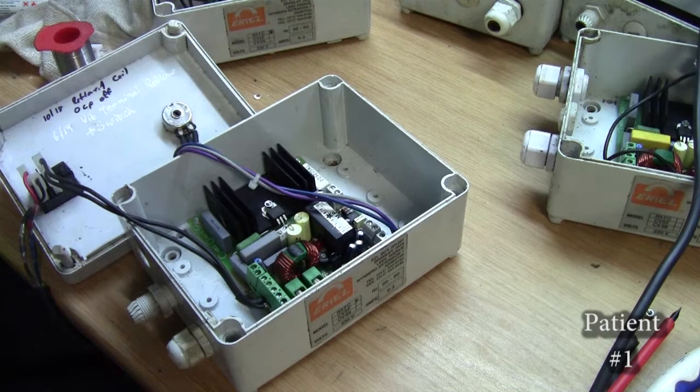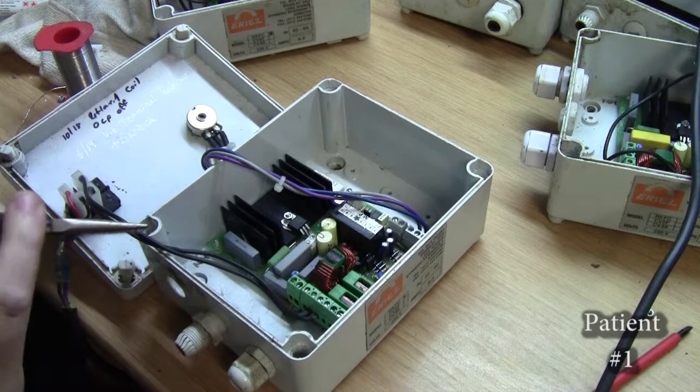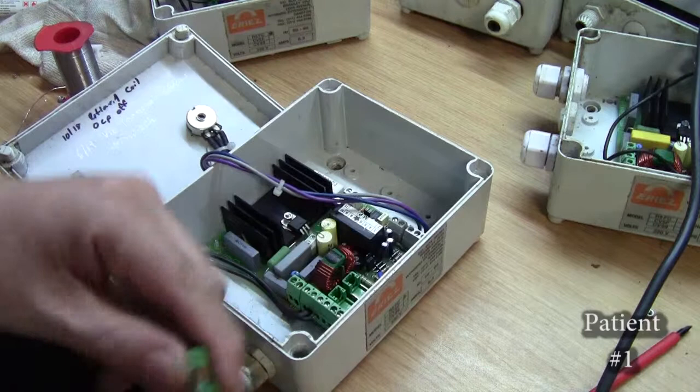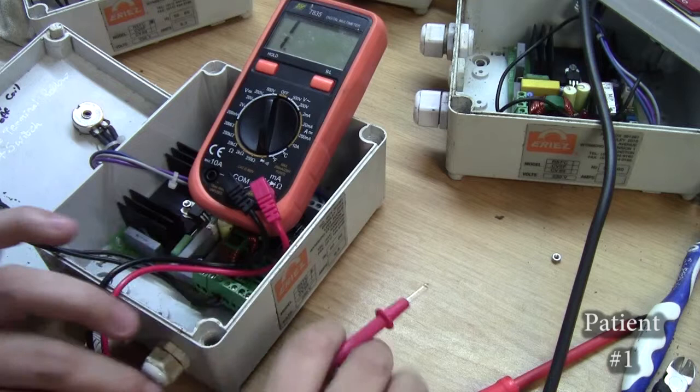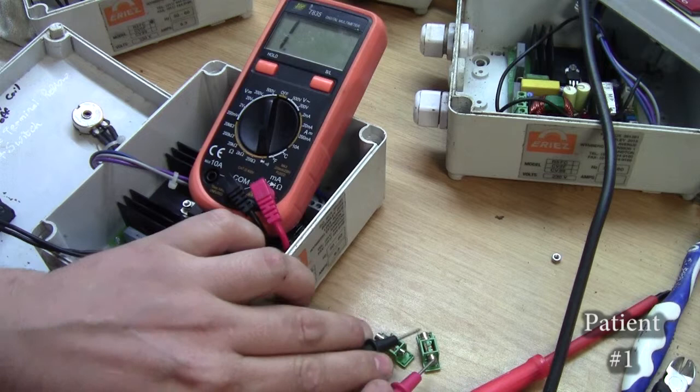Power switch is illuminating. The rest of the control board is dead. Okay, that overcurrent, that arcing might have caused a plasma arc and overcurrent. So let's pull the fuses and see if we haven't blown a fuse in this unit. That fuse is open circuit. Let's try the other fuse. Okay, so we have got two blown fuses.